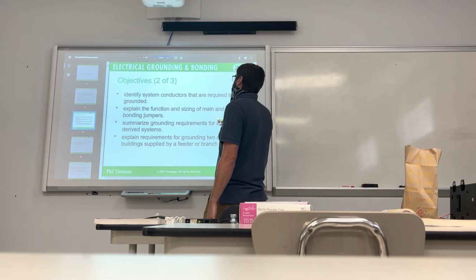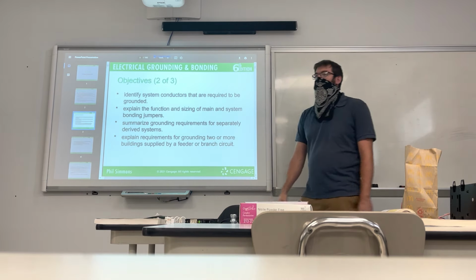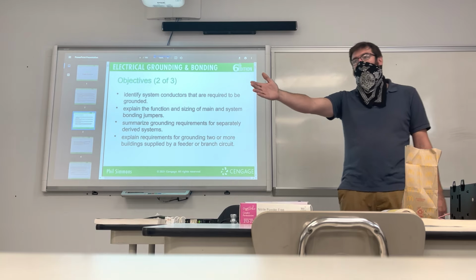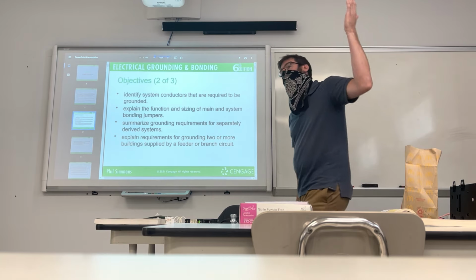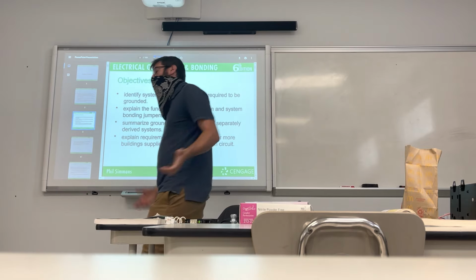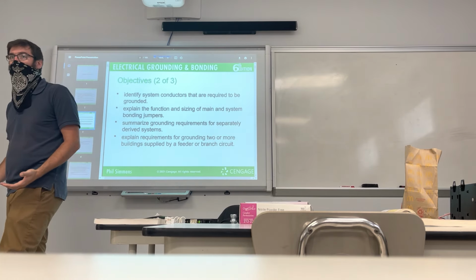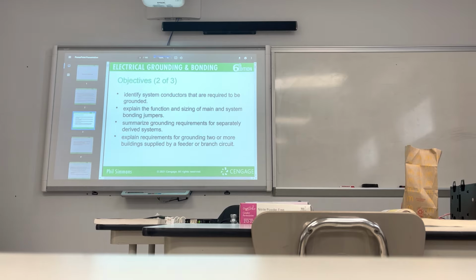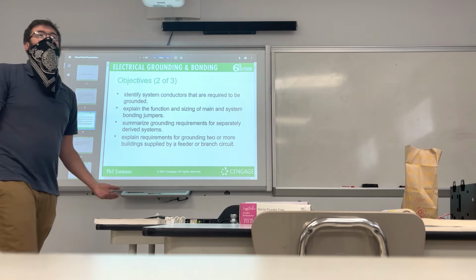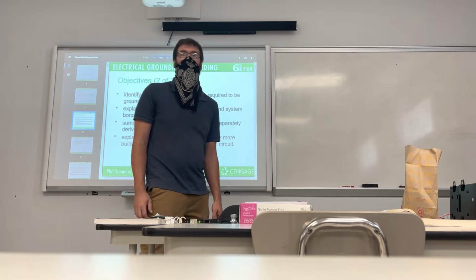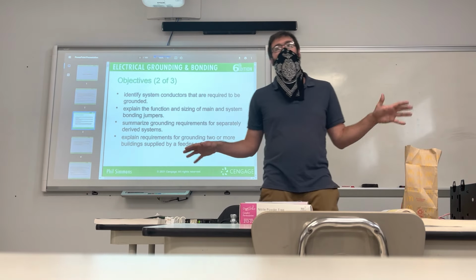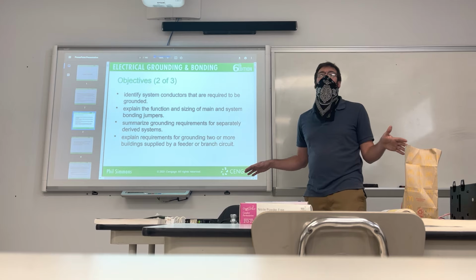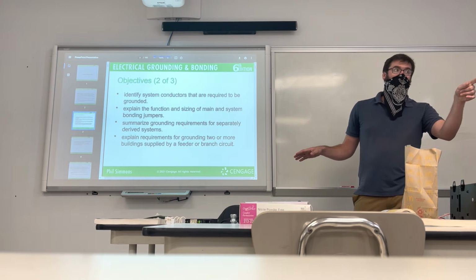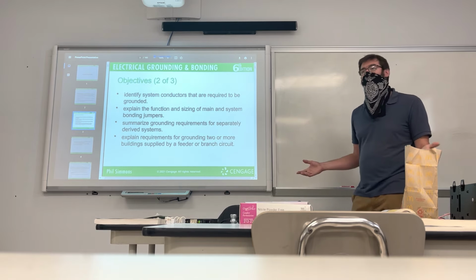Explain the function and sizing of the main system bonding jumpers. What's a big thing that we think about with those bonding jumpers? They don't have to carry the full load of the circuit, right? If we're bringing in 4-aught as our hots, our ground wire is not 4-aught, is it? No. Why? It only needs to hold a split second. Not a split second, but a second or two at most, perhaps, right? It doesn't have to carry that long term. It's not a continuous load. It doesn't even see power normally, under normal operation. Should there be any power going over a ground? Absolutely not. It should be a low impedance system.